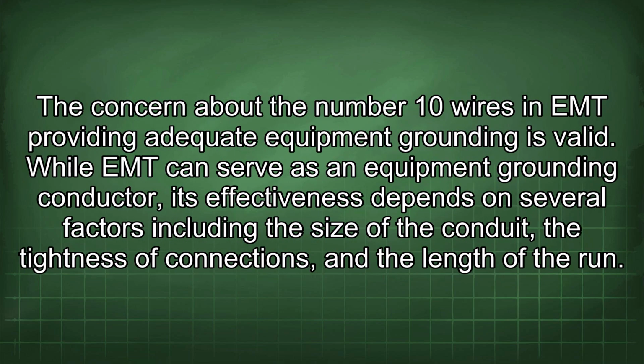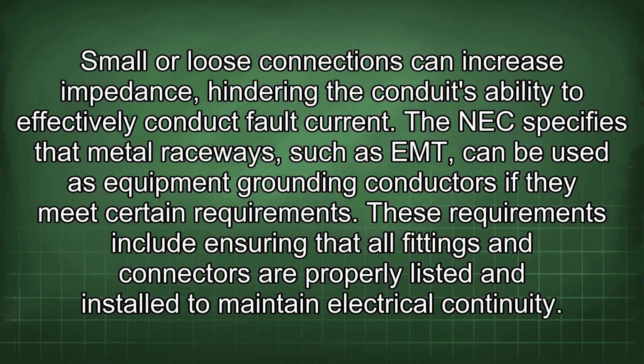The concern about the number 10 wires in EMT providing adequate equipment grounding is valid. While EMT can serve as an equipment grounding conductor, its effectiveness depends on several factors including the size of the conduit, the tightness of connections, and the length of the run. Small or loose connections can increase impedance, hindering the conduit's ability to effectively conduct fault current.